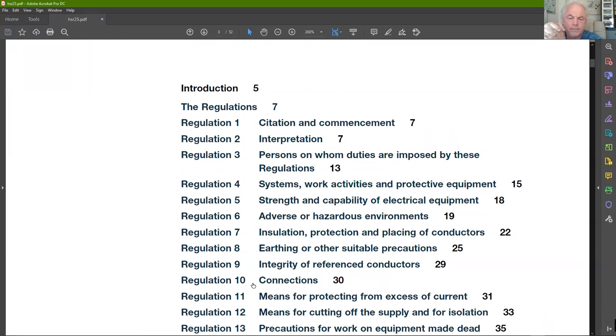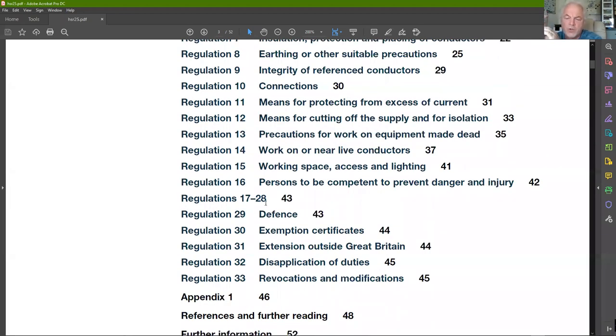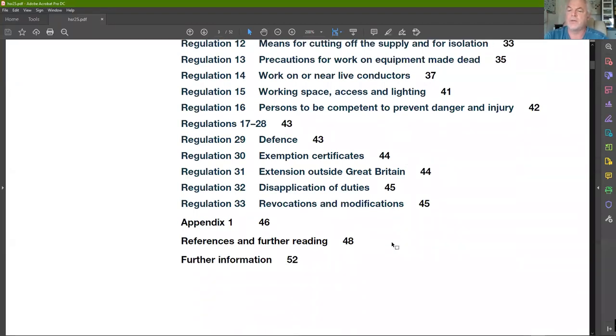You've got poor connections — go straight to Regulation 10. You've got issues with earthing, identification, or the installation — it's all in here. Some of your normal codes might result in non-conformities with the Electricity at Work Regulations, giving much better information to give to your clients. Sean in the chat is noting the use of the word 'systems' rather than 'installations' — we were talking about BS 7909 the other day, which covers temporary electrical systems for events.